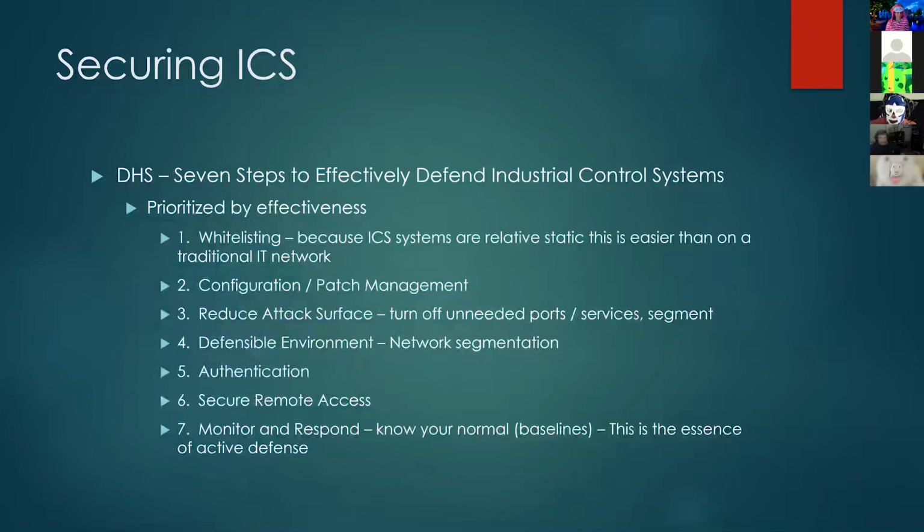Now, this is one that I think should be a little higher up on the list, because every successful attack on an industrial network that I'm aware of has started out with some sort of credential harvesting, usually by social engineering. So if you keep people from using the same credentials on your industrial network as on your corporate networks, then you're going to get a big win right there.